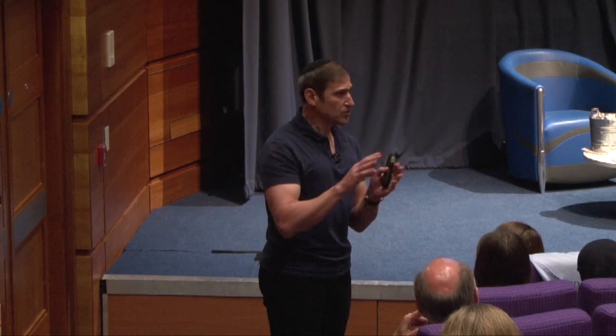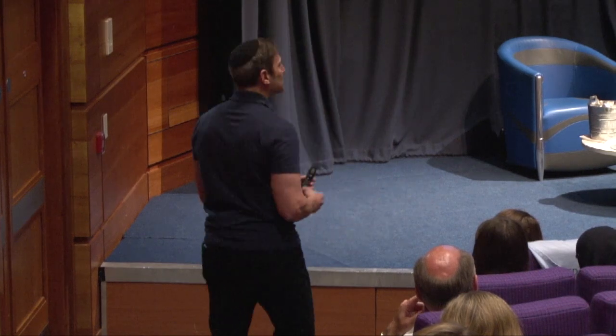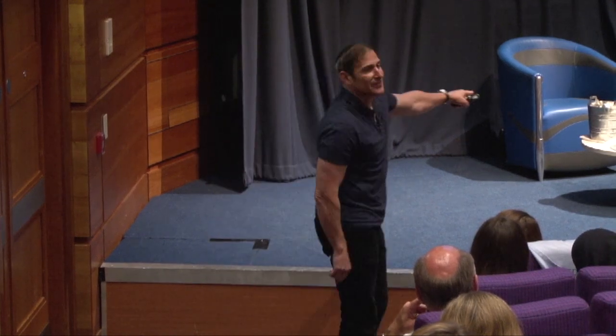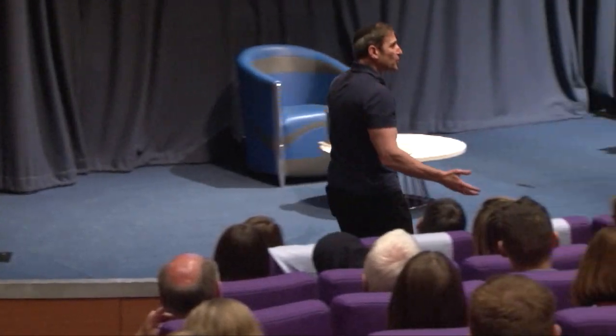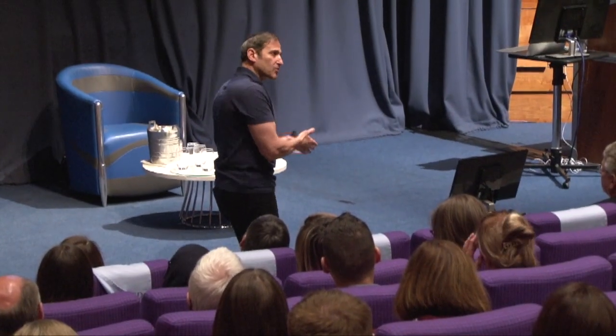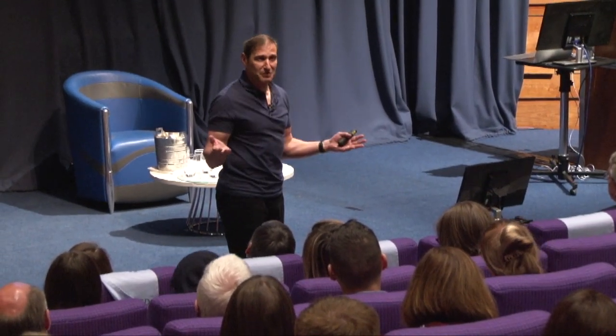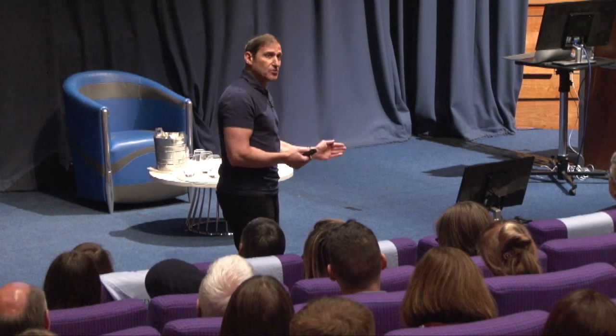Some people call it a static field gradient. Don't get confused. We'll get to the imaging gradients in a minute. This is not the imaging gradients. And that just means if I put a bar magnet on that table, as I get closer to it, I'm getting exposed to a stronger, stronger, stronger magnetic field. That's all it means, right? Here it's weaker, it's stronger here, it's stronger here.